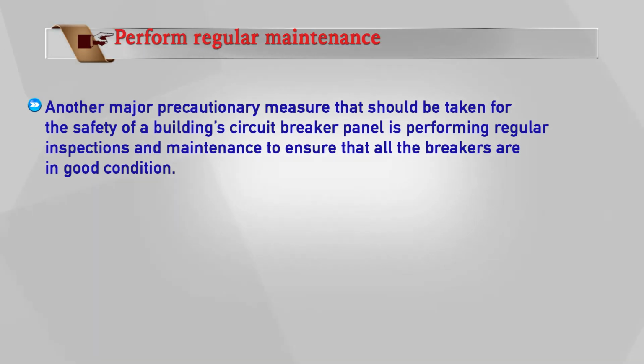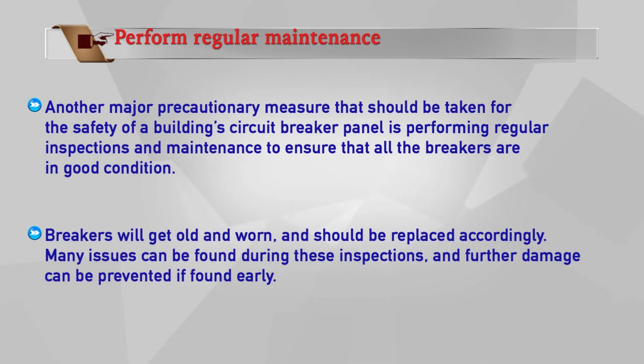Next point that you have to remember, you have to perform regular maintenance. Another major precautionary measure that should be taken for the safety of buildings is performing regular inspection and maintenance of the circuit breaker panel to ensure that all the breakers are in good condition. Breakers will get old and worn and should be replaced accordingly. Many issues can be found during this inspection, and further damage can be prevented if found early.